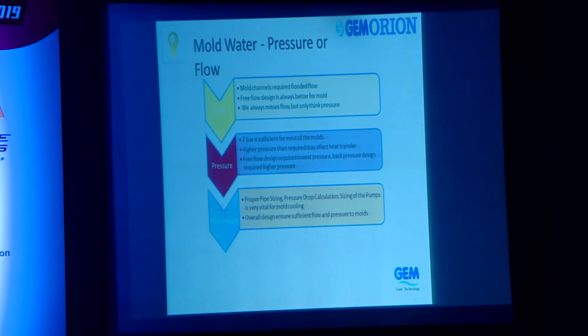very high flow also can affect the heat transfer coefficient, because the Reynolds number of water will be different and coefficients will change. So we should try to maintain a lower velocity. And when we maintain low flow pressure, automatically the back pressure, if you don't go for back pressure design, then the pressures can be reduced. This can be done by proper pipe sizing, pressure drop calculation, pump sizing, and is all vital for mold cooling, as well as the overall design ensures sufficient flow and pressure.